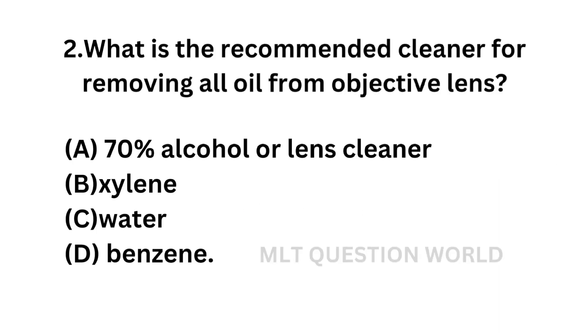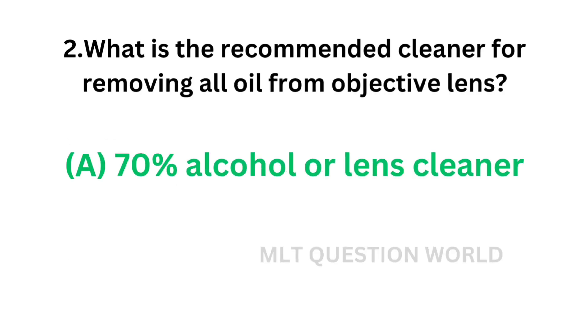Question number 2: What is the recommended cleaner for removing all oil from objective lens? Option A: 70% alcohol or lens cleaner. Option B: Xylene. Option C: Water. Option D: Benzene. The correct answer is option A. 70% alcohol or lens cleaner is used for removing all oil from objective lens.